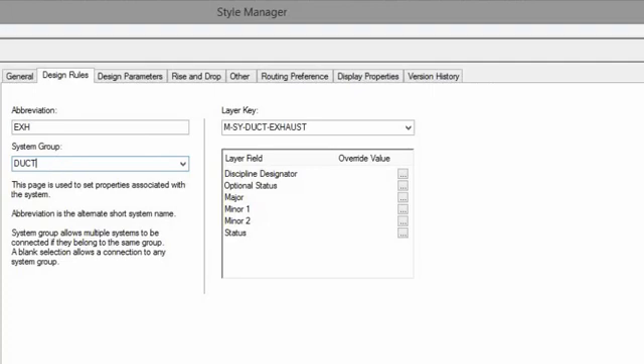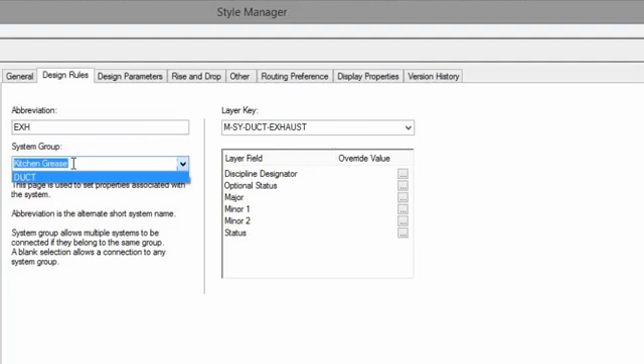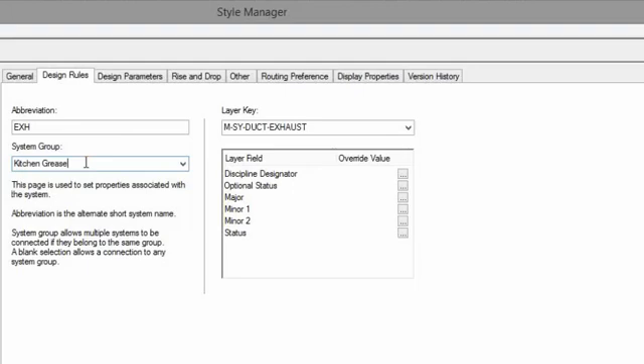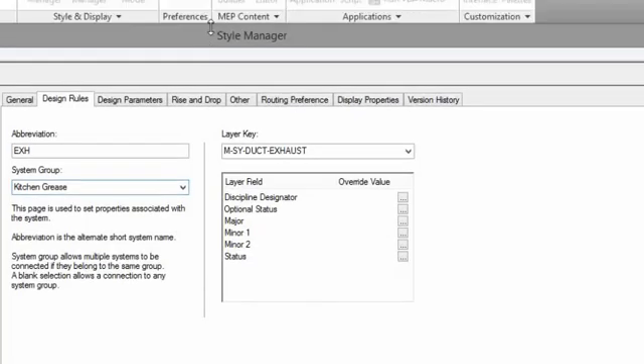But if I was to go ahead and add a, say, a kitchen grease system group, then look at that. What that's going to allow you to do is just to make sure that that took. Yes, it did. So now there's duct and kitchen grease. What that means, the system group means is you cannot attach a duct of a different system group to your current system group. So basically, I have a system group of kitchen grease. I can't, it won't allow me to attach supply air, return air, exhaust air to that system. Unless, of course, it also belongs to that system group. And it's not going to give you a pop-up warning or anything. It's just you're going to get the exclamation mark any time you try to connect two systems of differentiating system groups together.